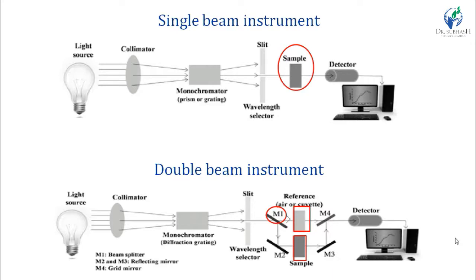In single beam instrument, only the sample is determined. In double beam instrument, the sample is determined in comparison to its reference compound. The radiation beam from the monochromator is split into two beams — one passes through reference and one through sample. After passing, the beams are combined if there is one detector, or kept separate if two individual detectors are used.